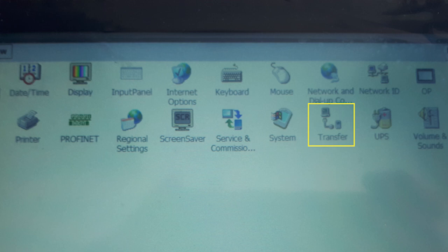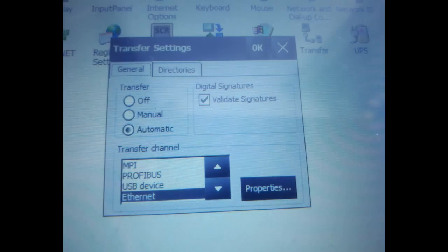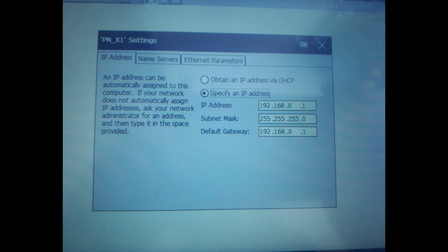After connecting the PC and the panel with Ethernet cable, make sure that the panel is powered on and its transfer channel is set as Ethernet. Check the IP address and the subnet mask, then go back to your laptop and open ProSave.